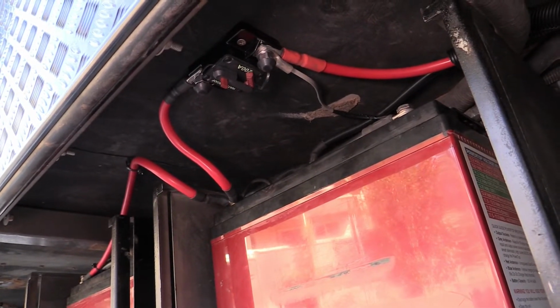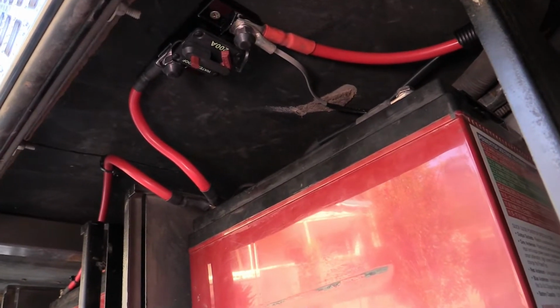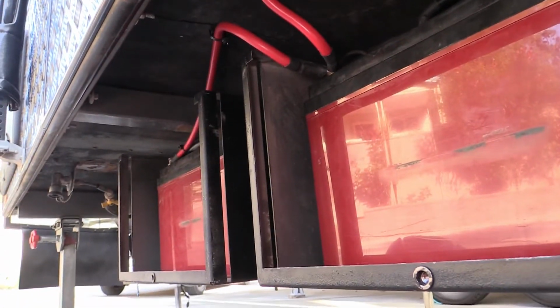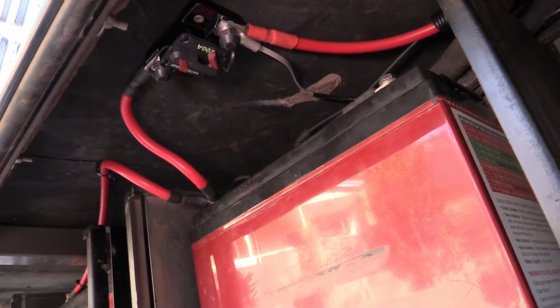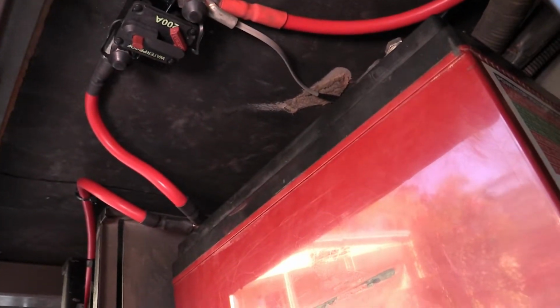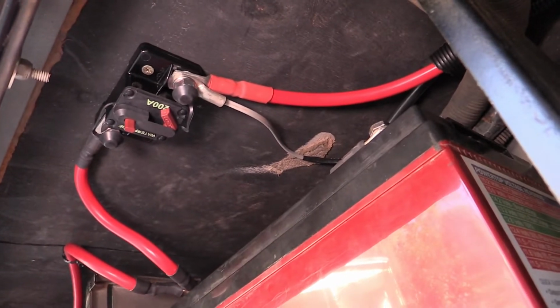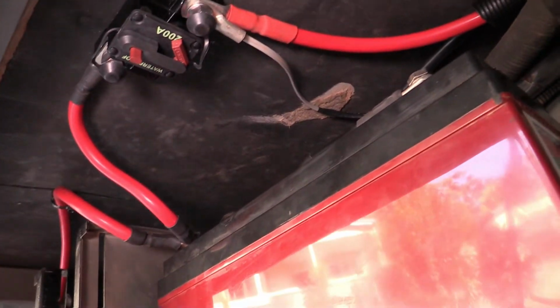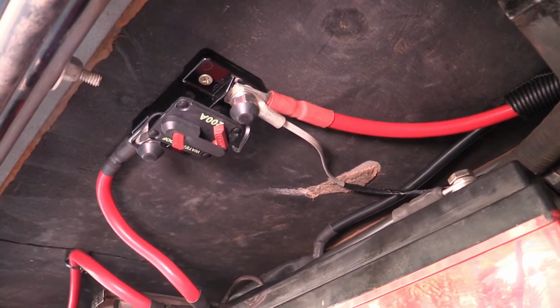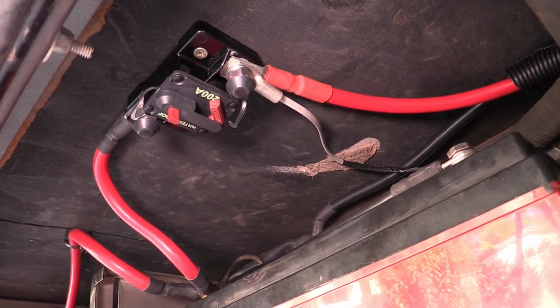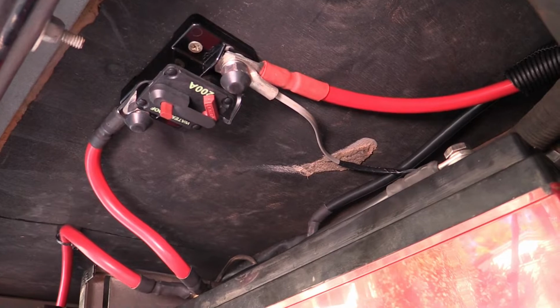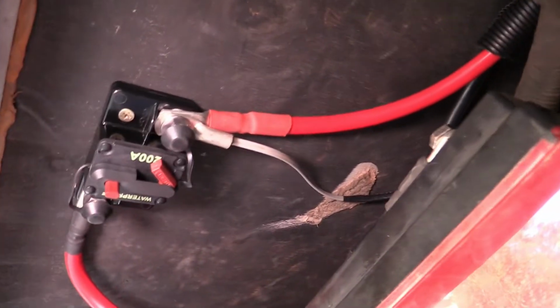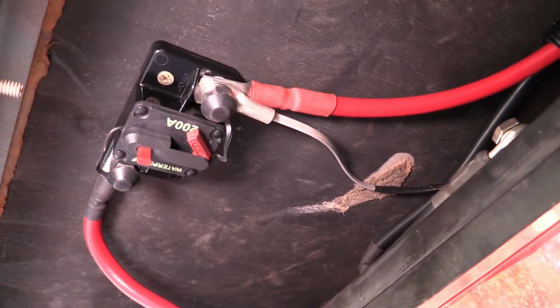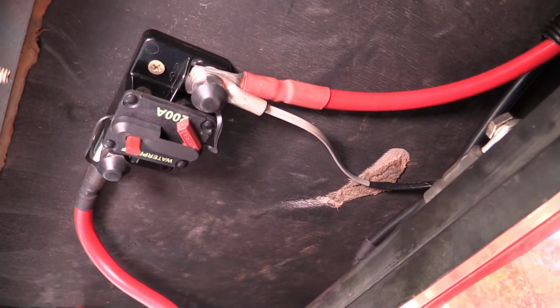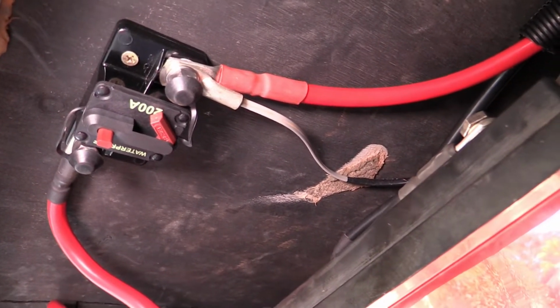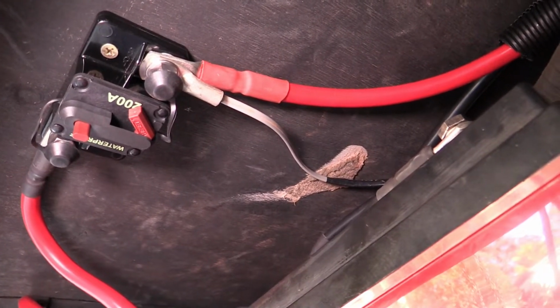Well, here's the finished job. The young fella's just gone - he didn't want to appear on camera, but he's done a very good job. The two batteries are reconnected with much heavier cabling, the same standard we ran up to the inverter. It's all passed through the shunt, which goes up to the battery meter above and indicates how much current we've used and are using. This replaces the fuse - it's a circuit breaker. If the current draws too much, it opens circuit, and we can reset it again without worrying about melted fuses.